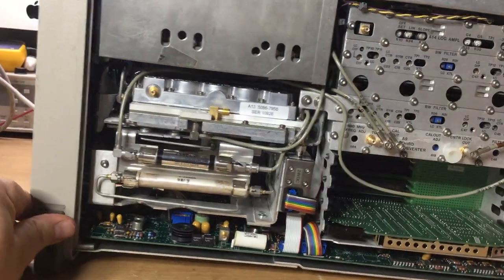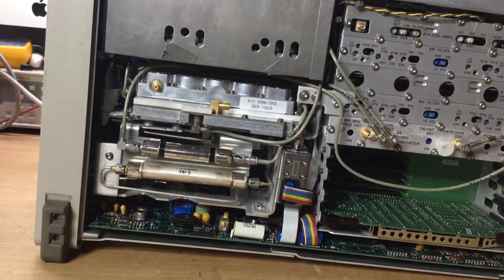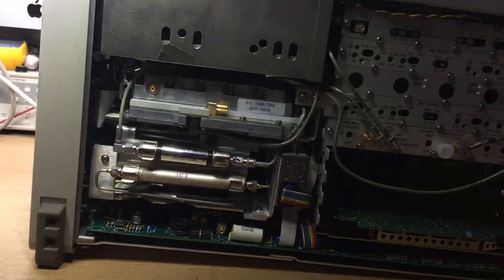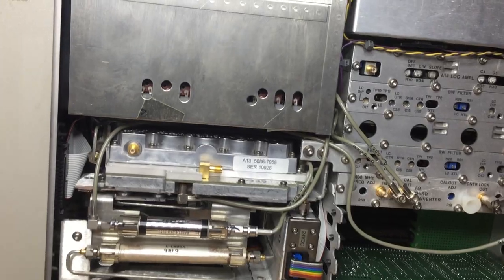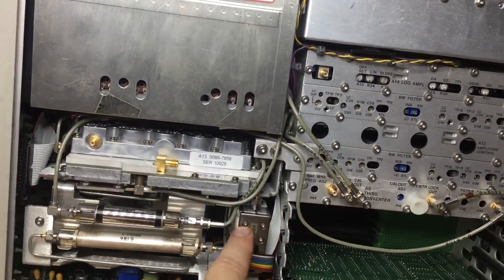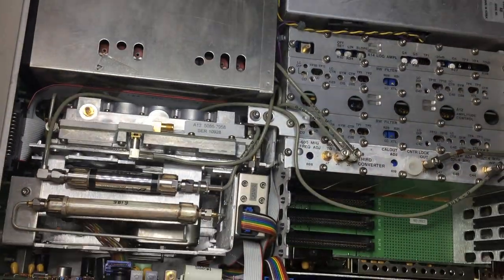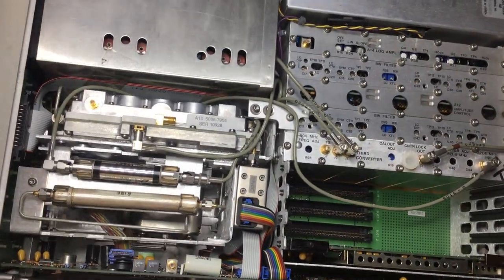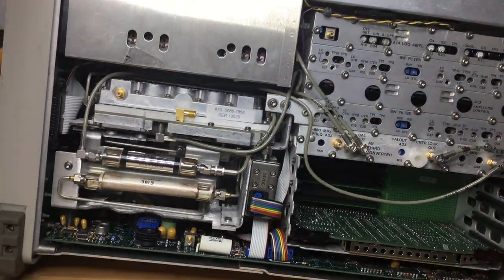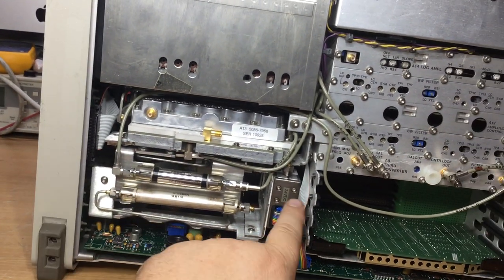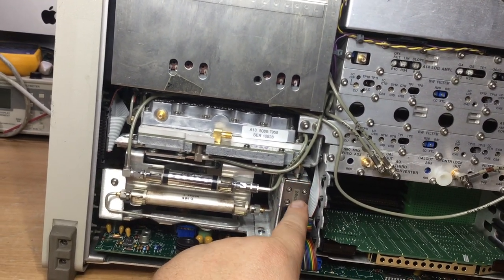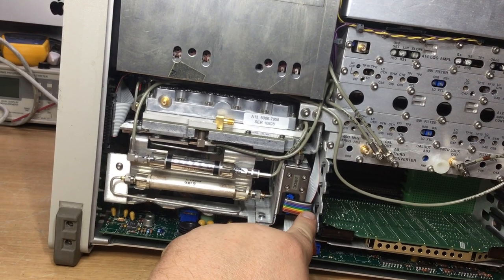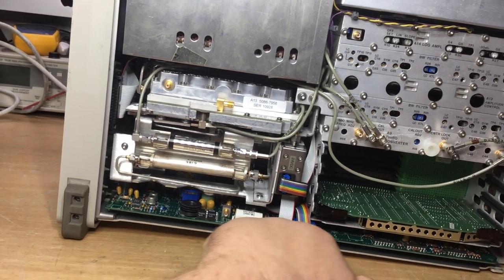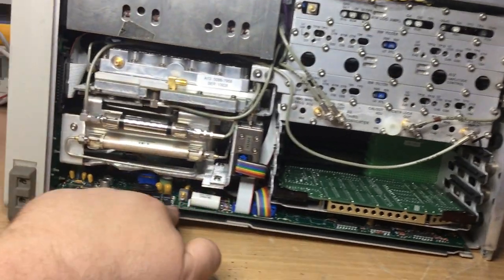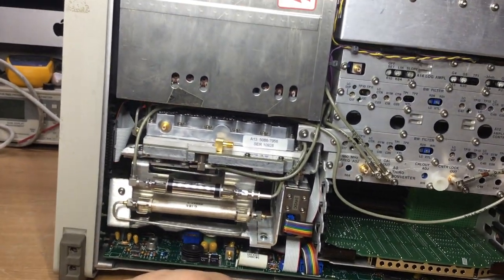But basically we've got the composition. It's quite a heavy instrument, it's a devil to move about on the bench, but basically top and bottom of it we have the step attenuator module there. I don't know if you can see down there, it's quite a long module. It goes from top to bottom of the test set. So that's where the RF input from the front connector connects through into there. And then the step attenuator is controlled via this ribbon cable, which connects to the microprocessor board, which is all of this board that runs across the side of the instrument.